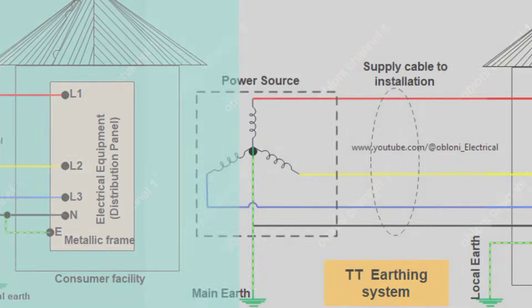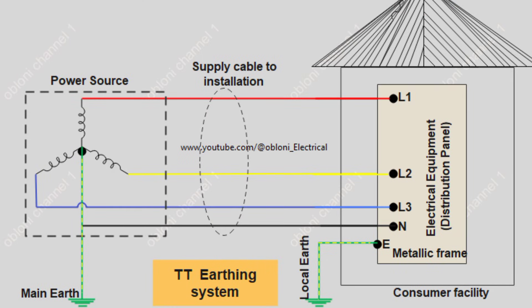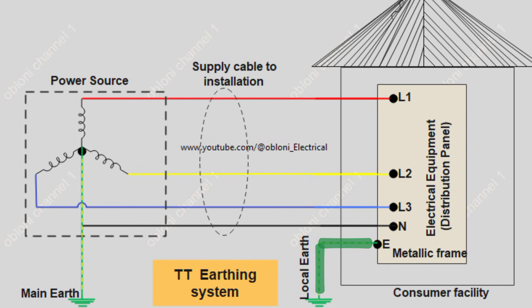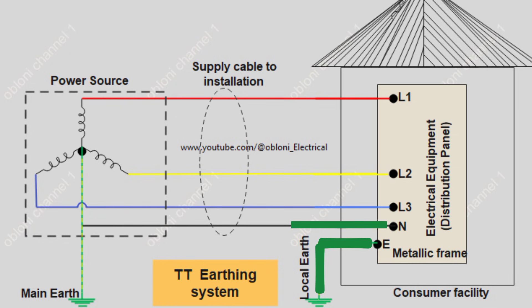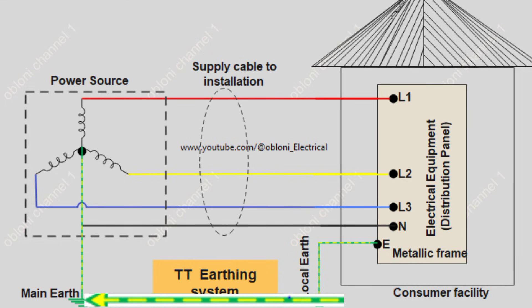The TT earthing system. In the TT earthing system, the neutral point of the power source is directly connected to earth, and all exposed conductive parts of the consumer installation are also directly connected to earth independently. The neutral and earthing conductors must be separate throughout the installation because the power supply distributor only provides the supply neutral to the consumer. When an earth fault occurs in the wiring, the earth serves as the return path for the fault current.